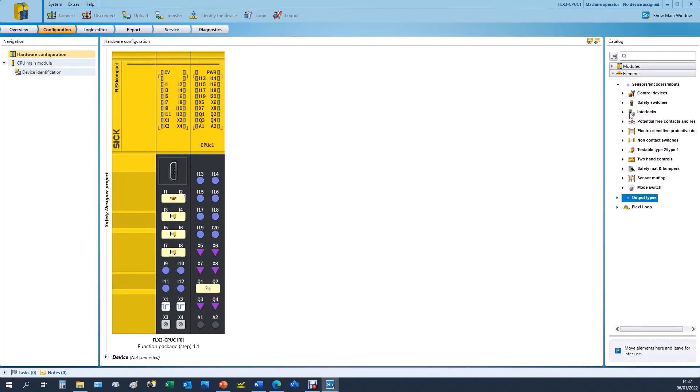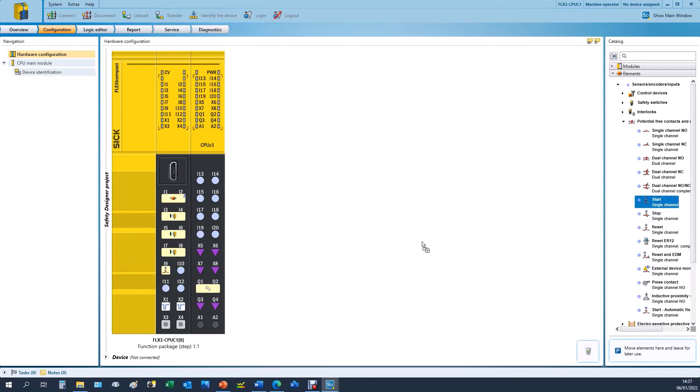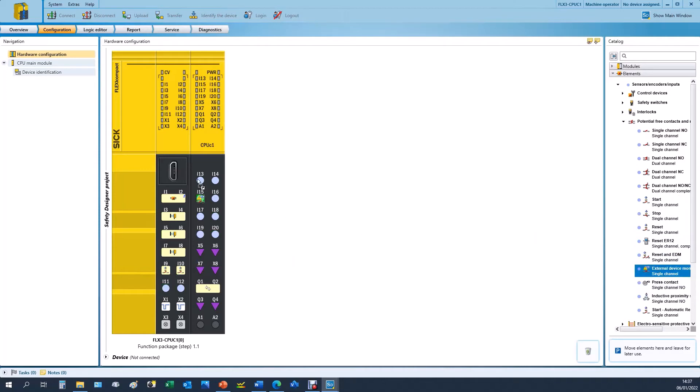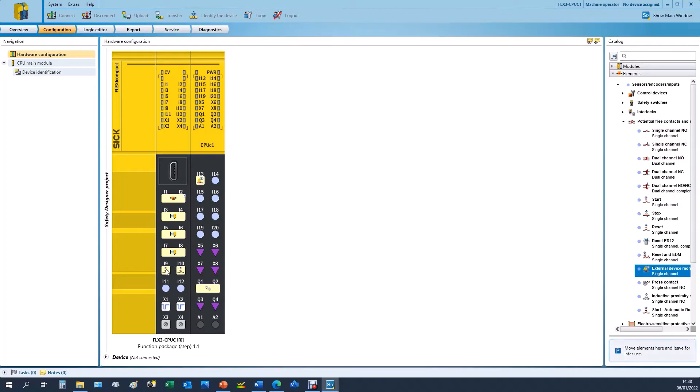I'll just go back to input devices because we actually need the reset and the start button, and what we'd normally like to see here as well is an external device monitoring input. This would be to monitor our contactors through the normally closed channel. This could also be wired in series with the reset circuit. However we're going to use a separate input for this. So we've added our elements and now we'll move along to our logic editor.